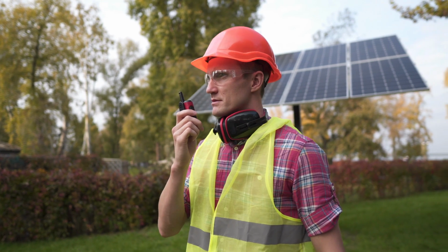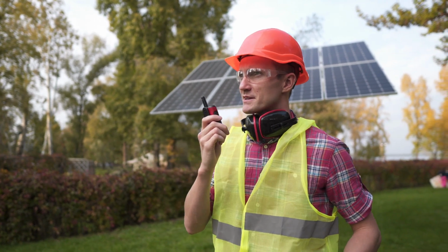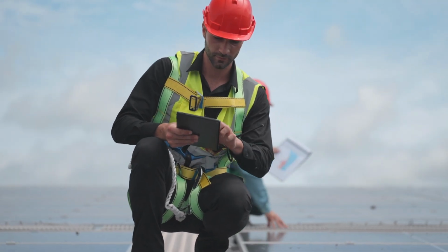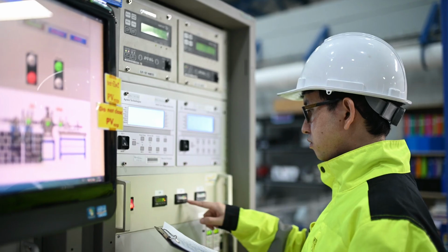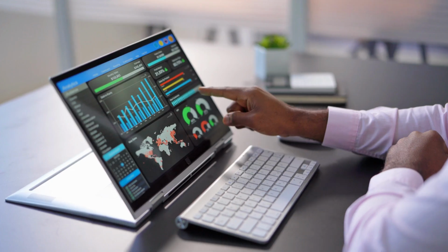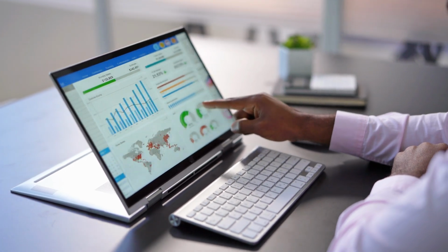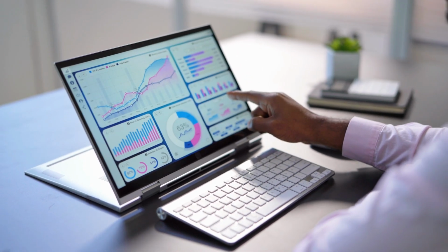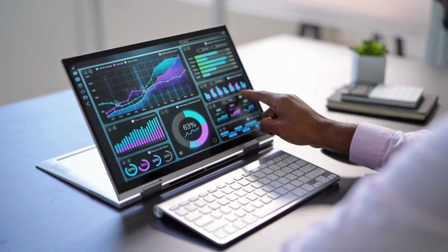Recently, we received feedback from a customer who noticed a negative active power value on one of the phases. They were concerned that the system might be exporting power to the grid, even though zero export had already been configured on the logger. After further investigation, we discovered that the negative value was actually caused by incorrect CT polarity.